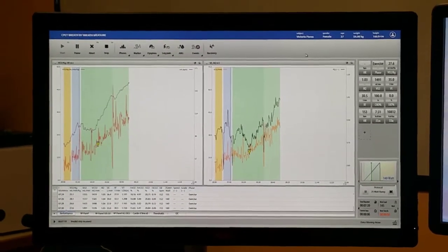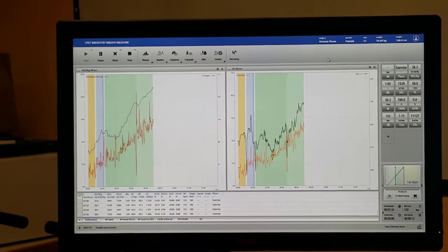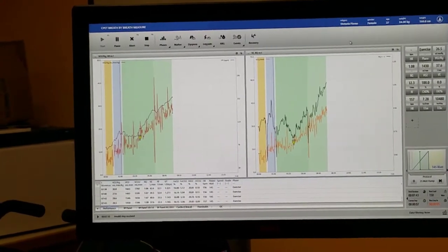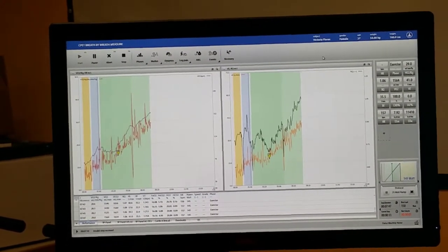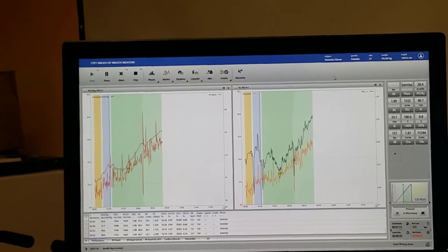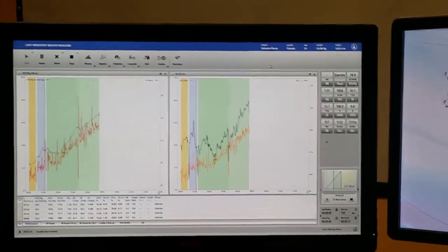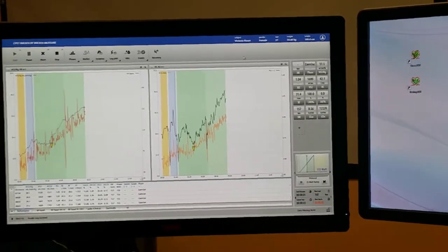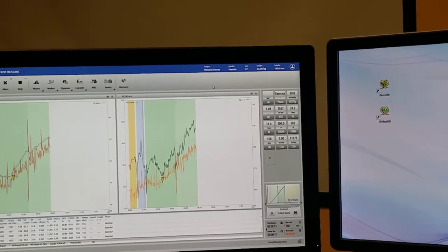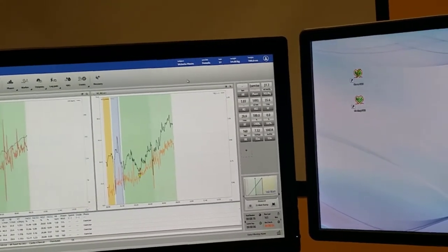Is there a way to make custom values too, if we're wanting to input them at different stages? Or a non-blood pressure, a miscellany. Let's say we're taking measurements of a third-party device, but we want to add it at this particular moment of the test. Yes, I do. So you want to take the manual blood pressures and add them in. You'll just indicate that you want to take blood pressure. Since we're not synced, because you can sync this with a Tango and it'll automatically kick out the signal for it to take it. But if you're taking them manually, you just click yes, and then you'll have access to the bar that'll say systole and diastole, and you can just punch them in there.